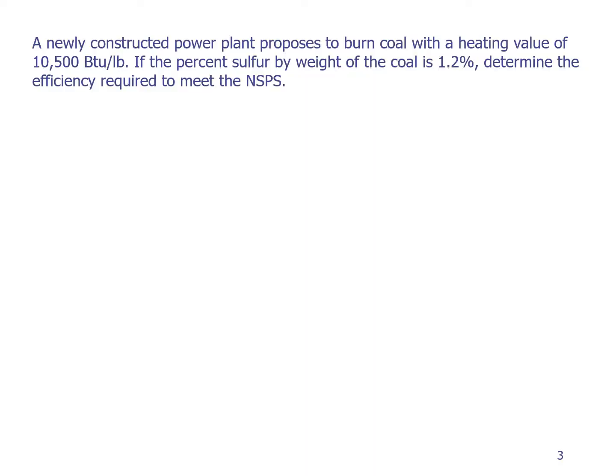So let's look at this example problem. A newly constructed power plant proposes to burn coal with a heating value of 10,500 BTUs per pound. If the percent sulfur by weight of the coal is 1.2 percent, determine the efficiency required to meet the new source performance standards. So what we need to do is first find the uncontrolled emission rate of SO2. This is the UER, and it will be in units of pounds per million BTU, because then we can go look up in a different table what the required control is.